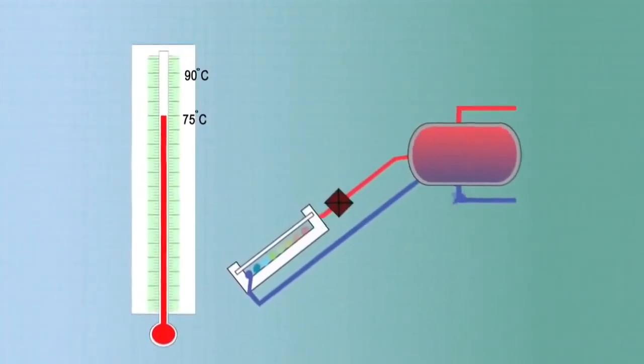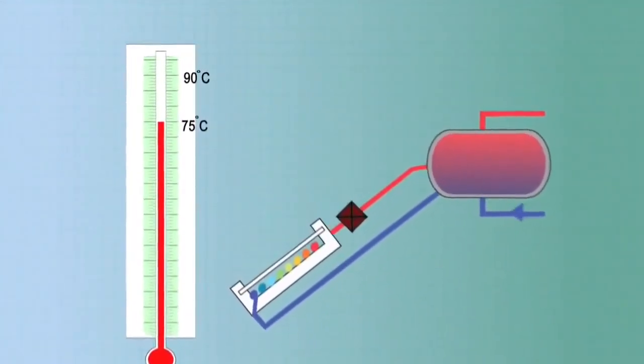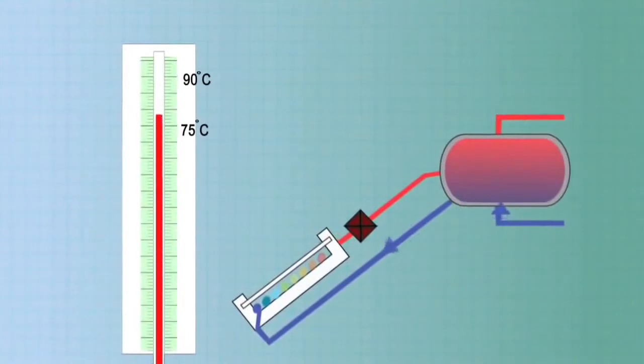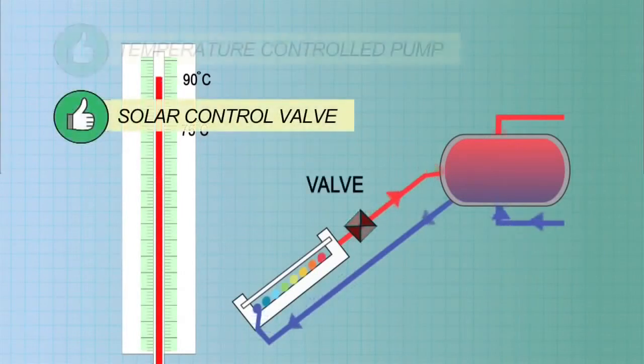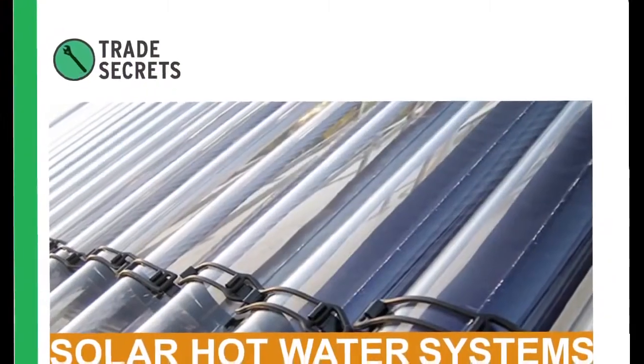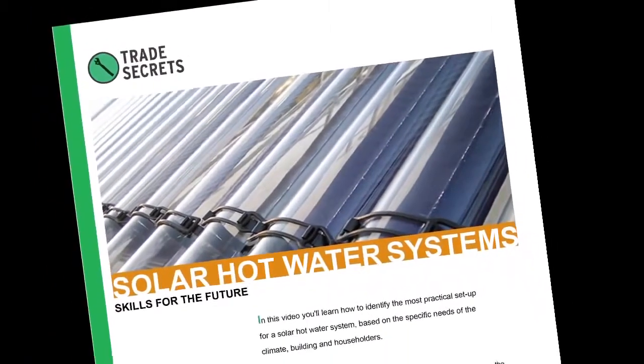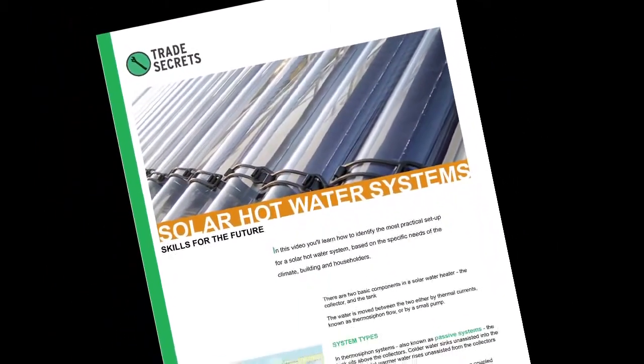The most common way to prevent overheating in the tank is by automatically stopping the circulation between collector and tank when the tank water gets too hot. This can be done using a solar control valve or a temperature controlled pump. See the fact sheet on the Trade Secrets website for more information about how to control for frost and overheating.